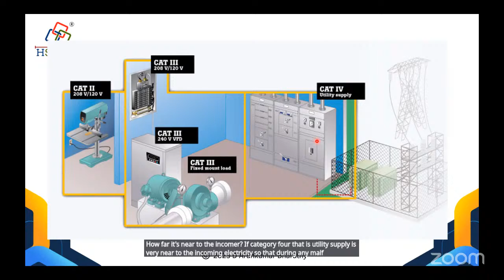So here, what we have to understand is: category means how far it is from the incomer. Category 4, the utility supply, is very near to the incoming electricity, so that during any malfunction, lightning, or other inductive load, you will get more fault current. So whatever instrument you use to measure in category 4, it should have the compatibility to handle that kind of emergency.